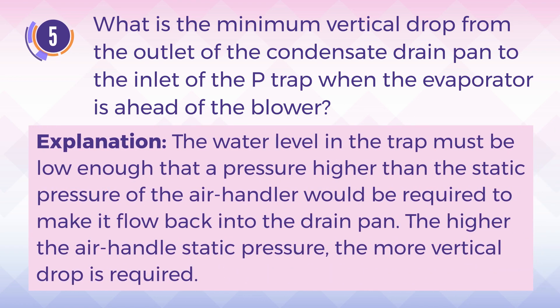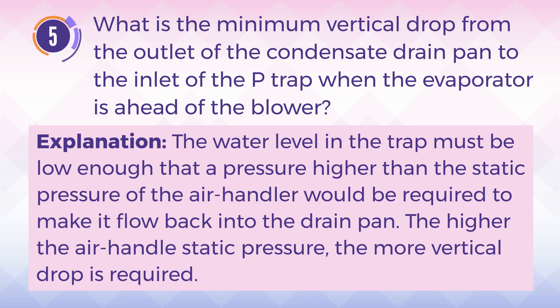Explanation: The water level in the trap must be low enough that a pressure higher than the static pressure of the air handler would be required to make it flow back into the drain pan. The higher the air handler static pressure, the more vertical drop is required.